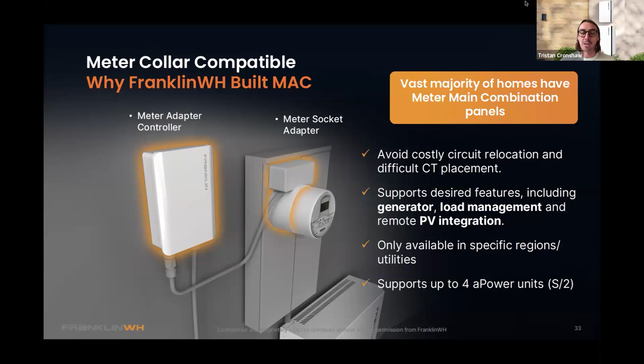Now, the third-party meter collars connect directly via an analog connection cable to the meter adapter controller, as you can see in this diagram. The aPower units connect via CAN bus communication, using a Cat5 or Cat6 cable, to the meter adapter controller. Essentially, we've removed the EMS, the energy management system, from the A-gate, and put it into a small external enclosure, which is the meter adapter controller. That has all your low voltage connections, including the emergency power off low voltage button for first responders, RS-485 connections for the A-hub or AP box, as well as CAN busing for the aPower. So everything connects at the meter adapter controller in terms of communication, but the islanding effect, or the grid relay, is in the collar. This aPower in this example would connect with its breaker - the AC output - onto the main bus bar or some other point of distribution at the home.